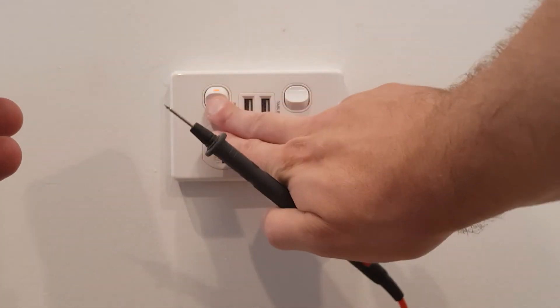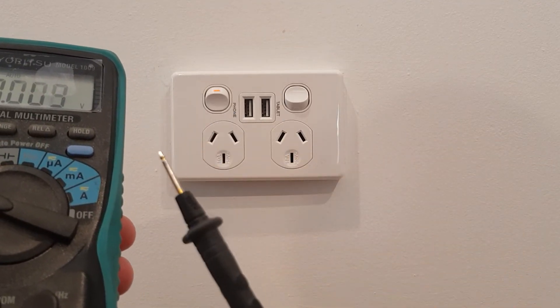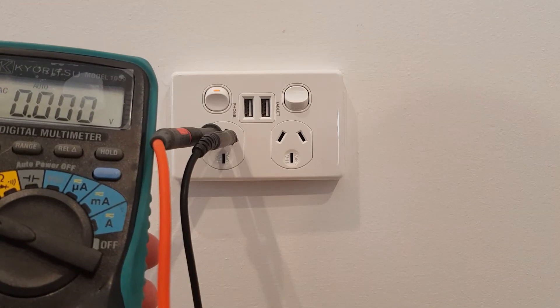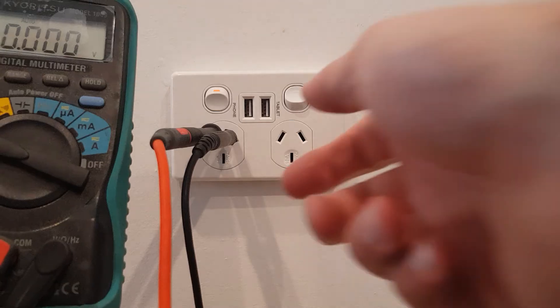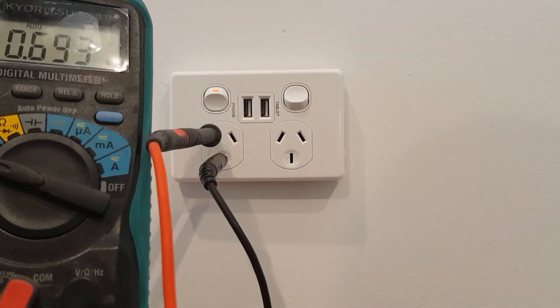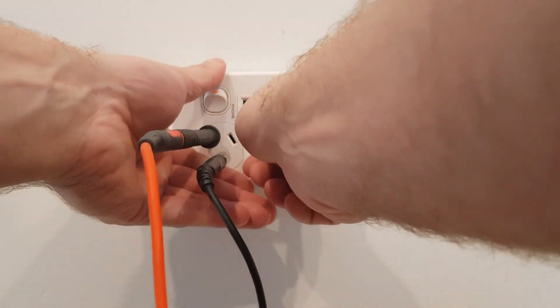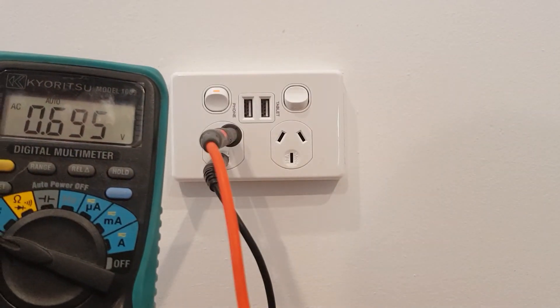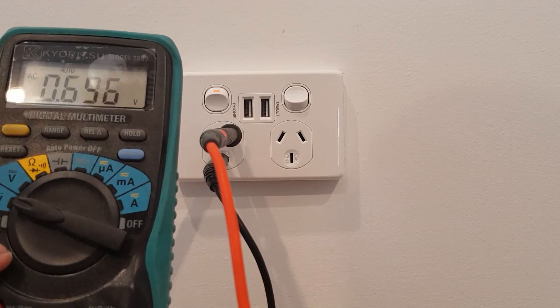Once you turn your power on, go to the switchboard, come back, voltage AC — put one pin of your multimeter in the active, one in your neutral and you should read 230 volts. Then if you pull it out of your neutral and put it in your earth, you should have 230. Then if you pull it out of your active and put it in your earth, you should have zero. That way you know your PowerPoint is wired correctly and you haven't put a cable in the wrong terminal.